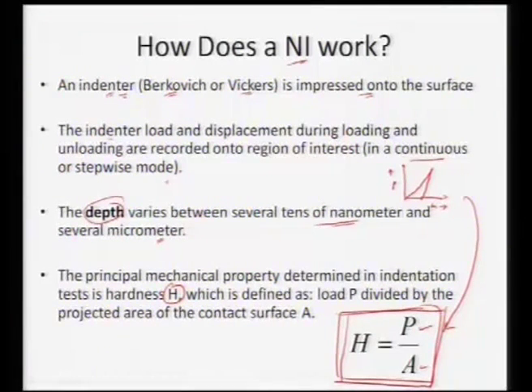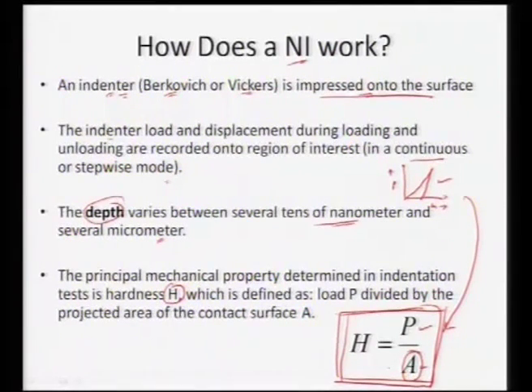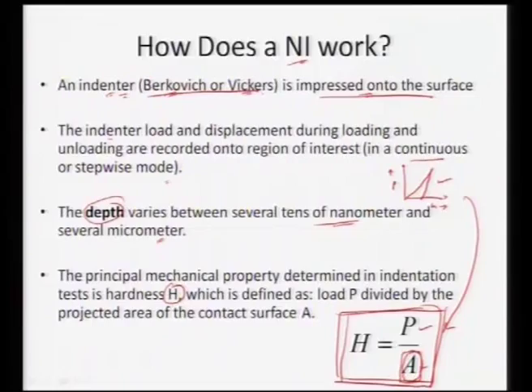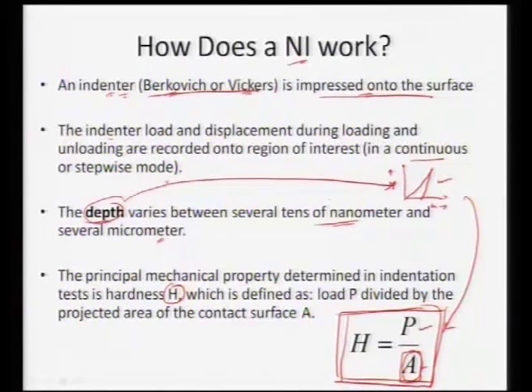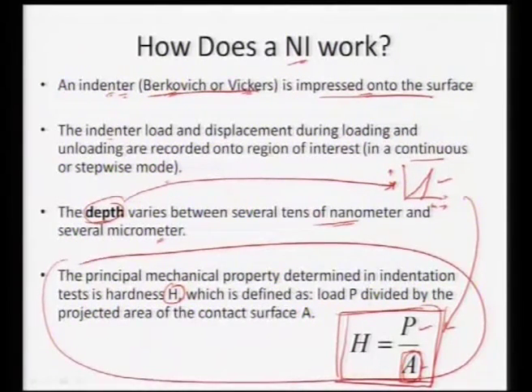Hardness can be calculated through measurement of load and area. We utilize a particular indenter — Berkovich, Vickers, or conospherical — impressed on a surface, and we measure the continuous loading and unloading. Measuring the contact area is not easy as in regular bulk testing, because Berkovich, Vickers, or conospherical tips may not have a perfect geometry. To address this, we always utilize standardization or calibration of the tip to measure the contact area with respect to the depth of the material.